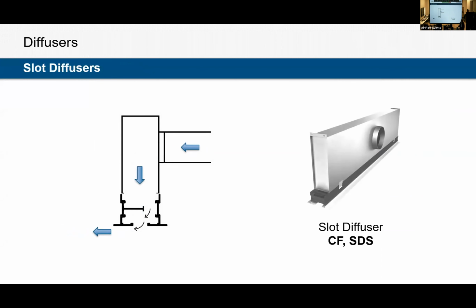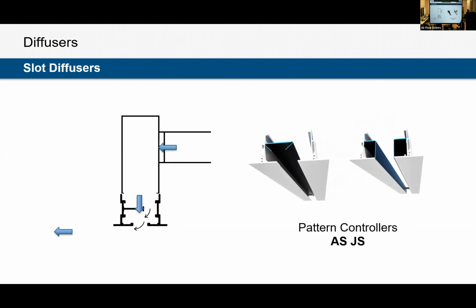All right, slot diffusers. On the room side, you're usually only going to see a nice continuous slot in the ceiling. It could have a frame on it, or could just be a skinny opening in the ceiling that nobody even notices. High-end retail spaces love to use slot diffusers. There are numerous different airflow patterns out of slot diffusers. This graphic shows a horizontal throw pattern, but we can go horizontal in either direction or straight down vertically out of the slot. It just depends on whether we're washing a window, or designing for normal overhead, trying to shoot across the ceiling, with different configurations for both options.